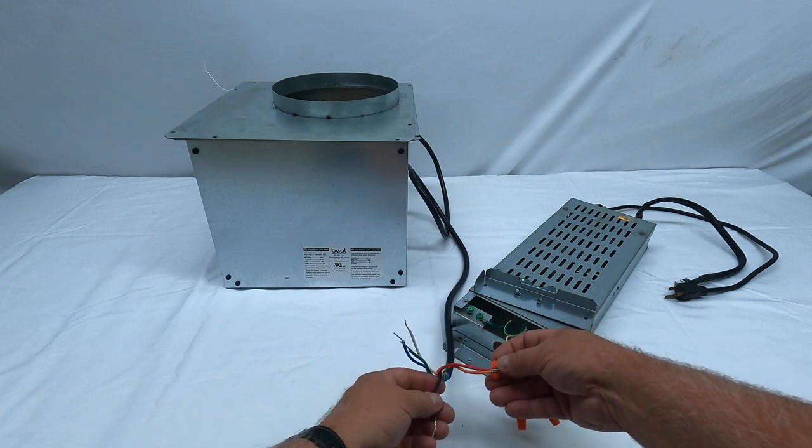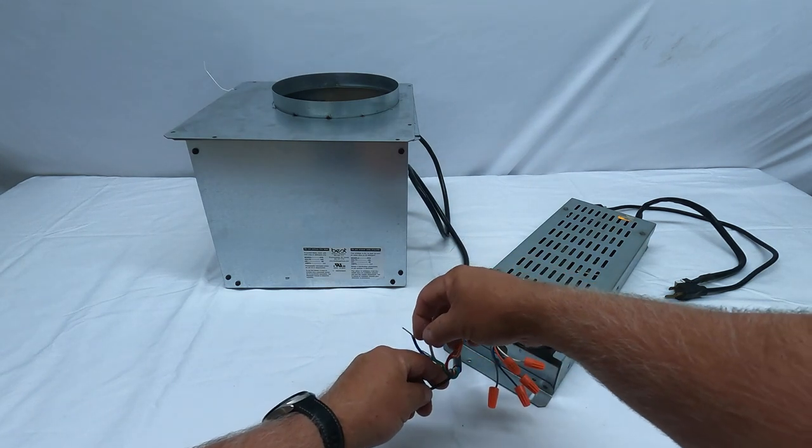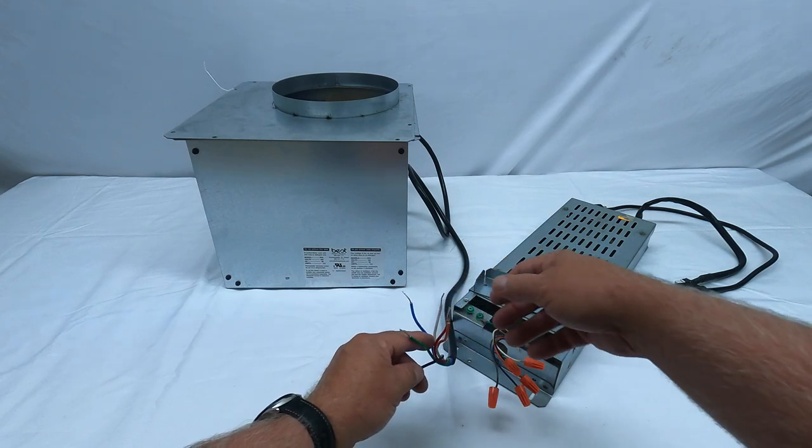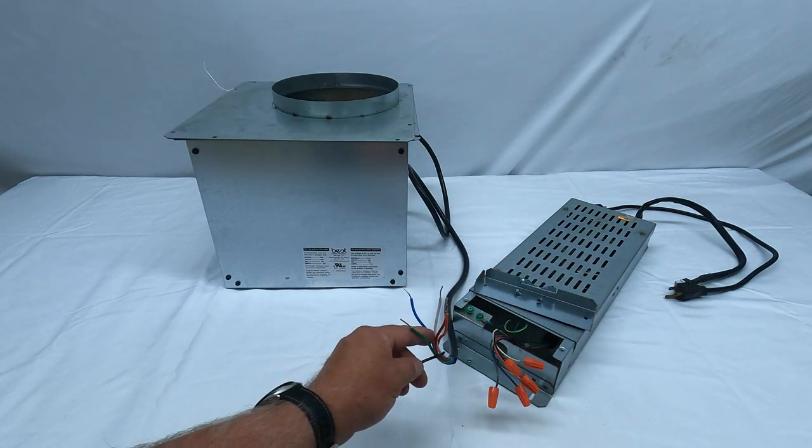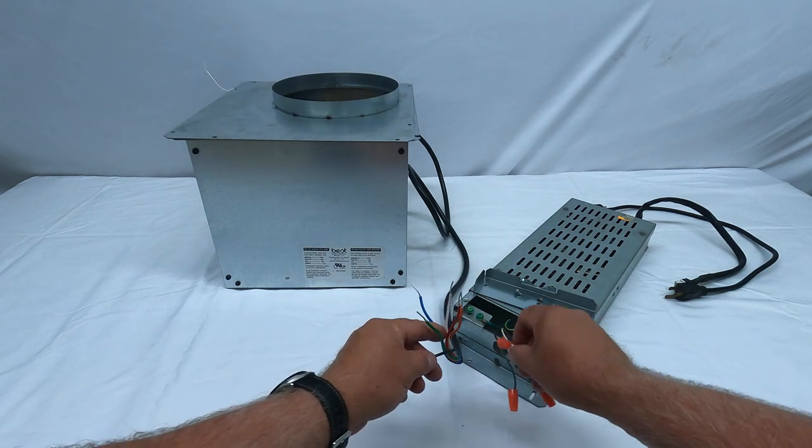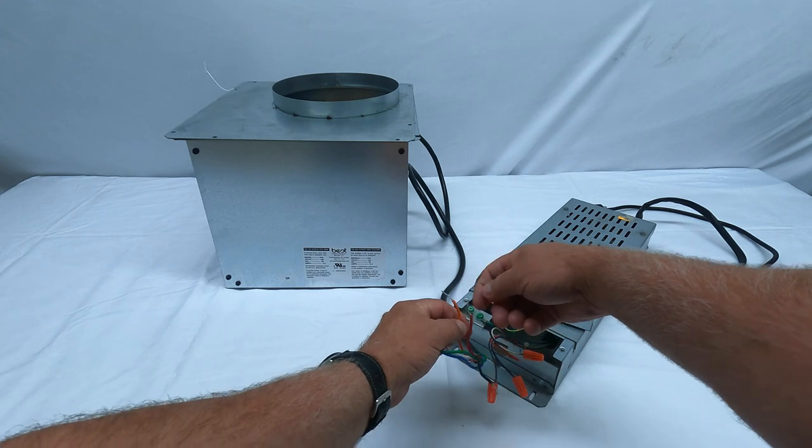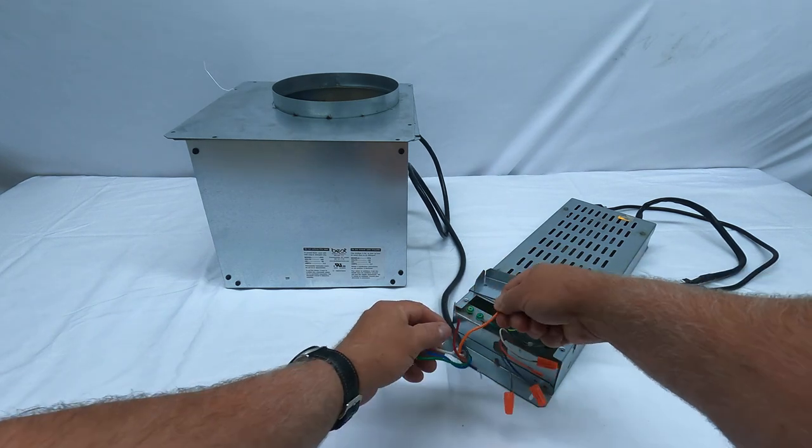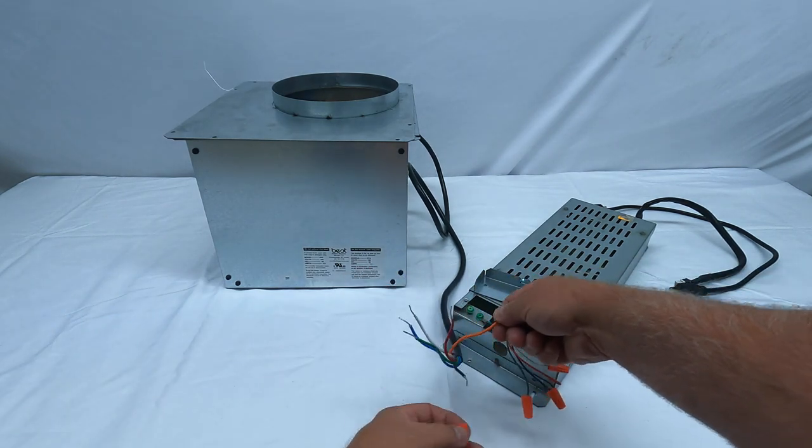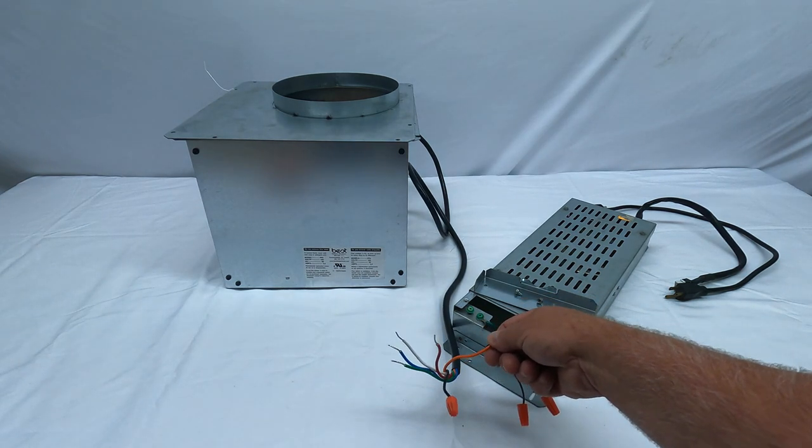And white to white. So I'm going to repeat it one more time because it's a little confusing. You're going to take green to green, blue to blue, red to gray, orange, orange and the black from the electrical assembly, and you're going to put a wire nut on this black wire coming from the PF6 blower, and white to white. And that will limit your speed to 400 CFM.